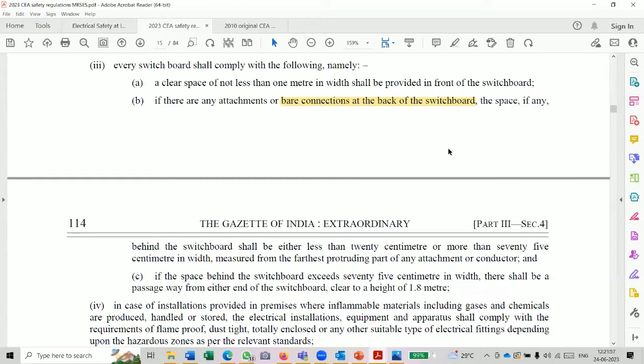Actually, there is some change from the previous one, it may be some typographical error or some unintentional insertion. This is wrong. If there are any bare connection, people will have to move to the backside and they have to have more than 75 centimeter. If you restrict the entry to less than 20, it will be inviting danger. So you have to go through the previous regulation. Basically, sir, the bare conductor has to be removed, probably.